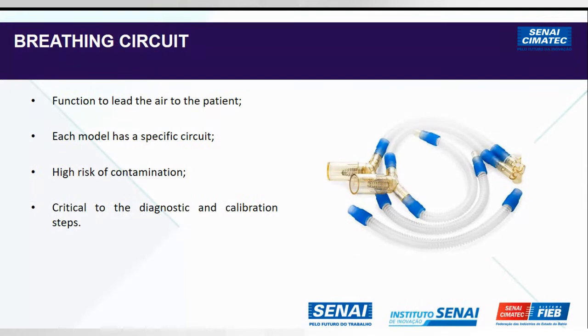Okay, the breathing circuits have the primary function of leading the air to the patients. Each model has a specific circuit because there are many different manufacturers, many different circuits. In some cases, the valve has a proximal circuit, a proximal line, and sometimes doesn't have the proximal line. They have many differences. It's very important that you send the ventilators with the complete breathing circuits. It's a high risk for contamination.